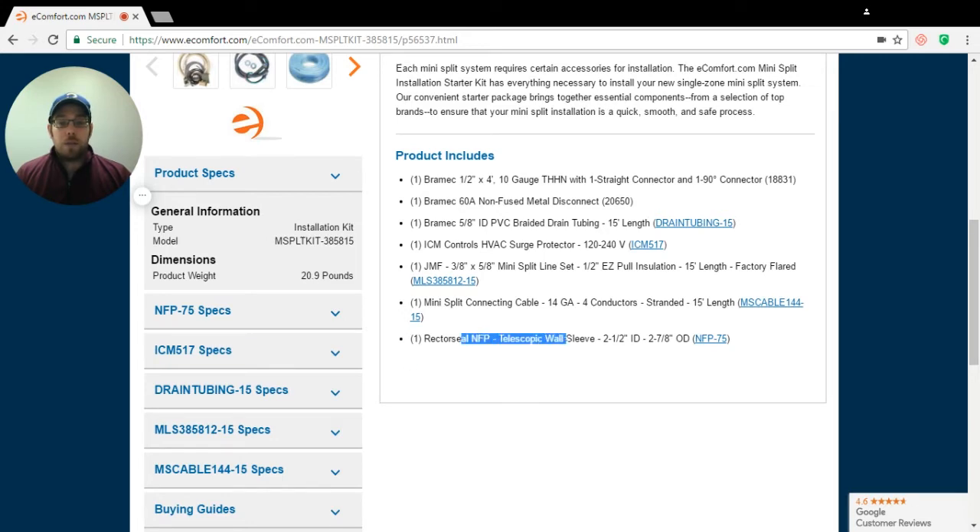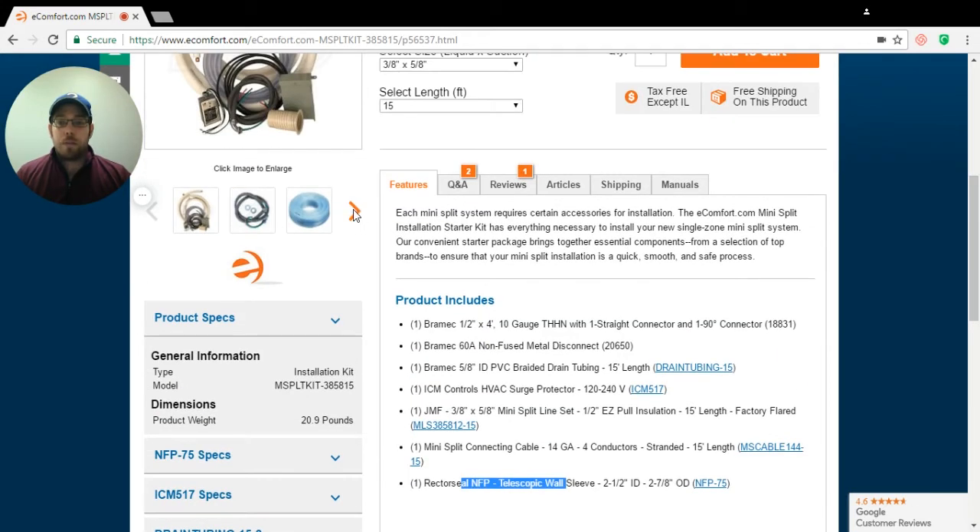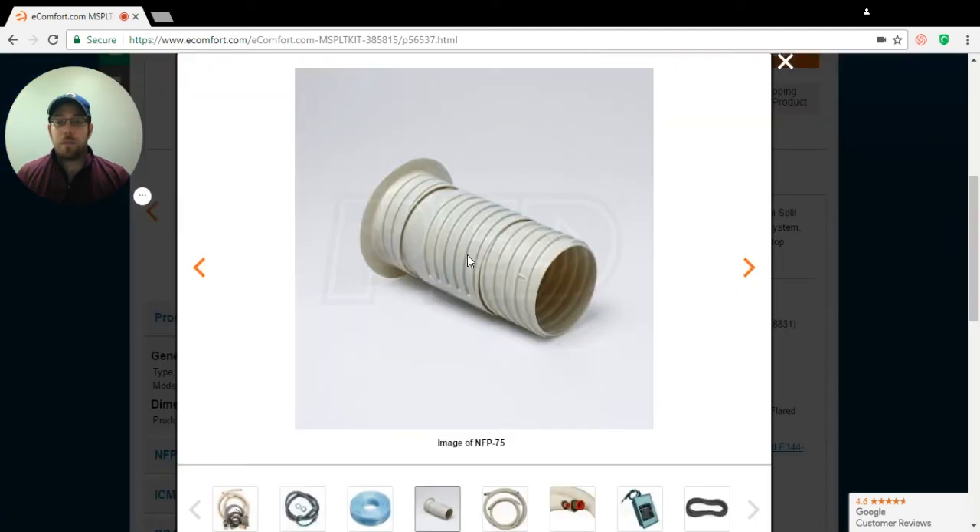And then your Rectorseal NFP telescoping wall sleeve. The wall sleeve — and I always like to bring this up — literally fits between your exterior wall and your interior wall. When you drill your 3-inch hole going through at a 10-degree angle, you're going to slide this in there. You can telescope it out so that it fits the full distance between the wall. Then you're going to be throwing your line set through there, your wire through there, and your drain tubing. This prevents any moisture going in between the wall, prevents any animals getting in, and it's a lot easier to run your line set and wire through.